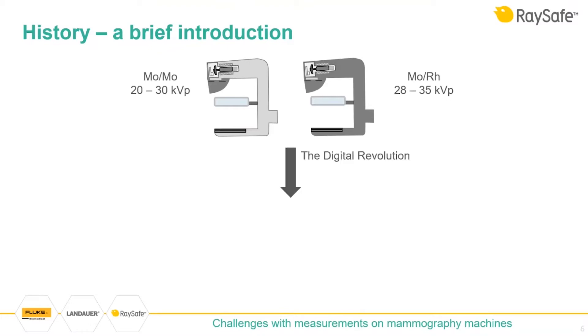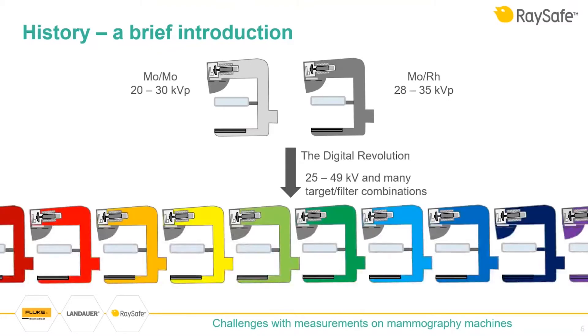A molybdenum filter was used at the lower end of the spectrum, and rhodium filter at the higher end. With the digital revolution came a lot of new challenges in mammography — new target-filter combinations, new acquisition modes, and a lot of behaviors that were never seen before. Measuring all these variations can be a huge challenge.